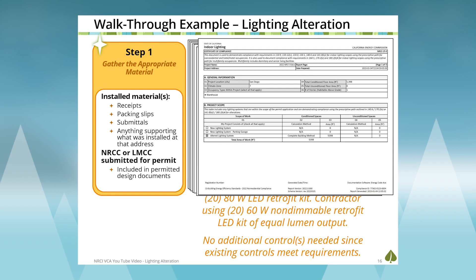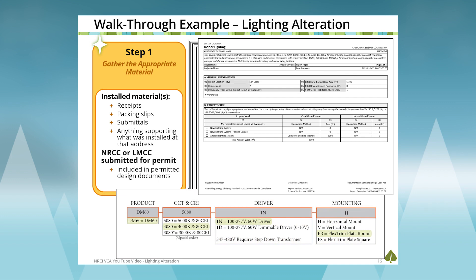We'll need the NRCC LTI, or if using the performance approach for lighting in conditioned spaces, the NRCC PRF or LMCC PRF. Note that lighting in unconditioned spaces cannot be included in the performance calculation, so sometimes you'll have two separate Certificate of Compliance forms, two separate compliance IDs, and two separate Certificate of Installation Forms for conditioned versus unconditioned spaces.